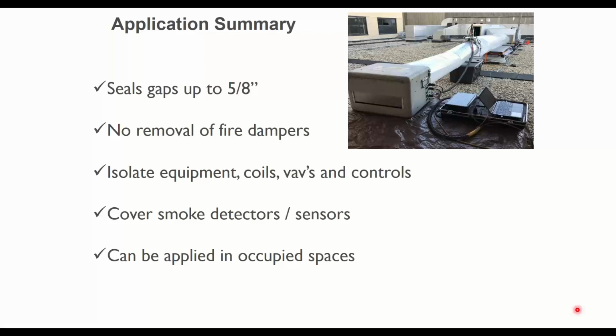But you can also isolate them with a VAV box. It's a little different than a residential damper. So typically, we'll put a piece of foam blocking upstream of the VAV box and seal up the medium pressure ductwork. And then later on, if you're going to do the whole duct system, we'll put a piece of foam blocking on the discharge side of your VAV boxes and seal up the low pressure side as two separate events. But anything else in the space like pressure sensors, humidity sensors, temperature sensors, we'll pull those out of the duct, put a piece of foil tape over them, seal everything up, and then put the sensor back in. Because we don't want glue going up into electronics, the sensors and stuff like that, and plugging them up.